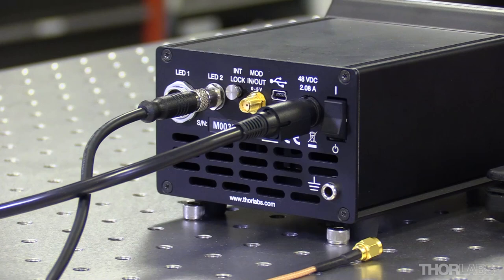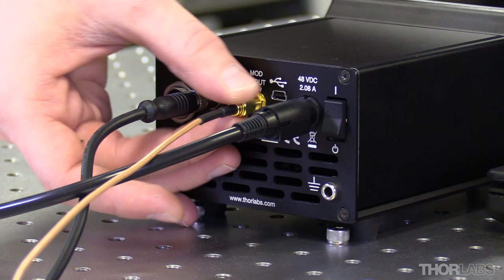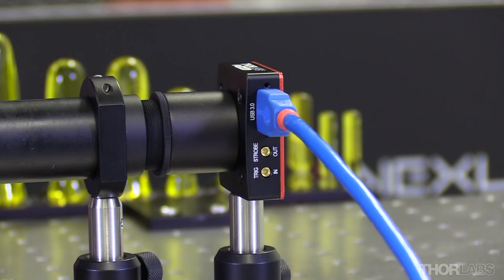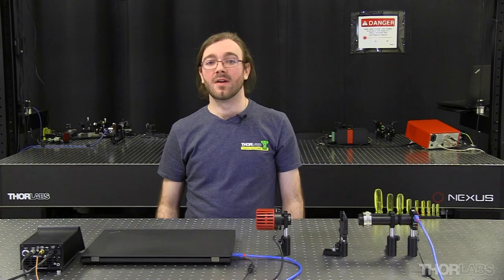Next the TTL output of the LED controller needs to be connected to the input of the camera. So here I'll connect an SMA cable to the mod in out of the LED controller. And here I'll connect the MMCX connector to the trigger input of the camera.